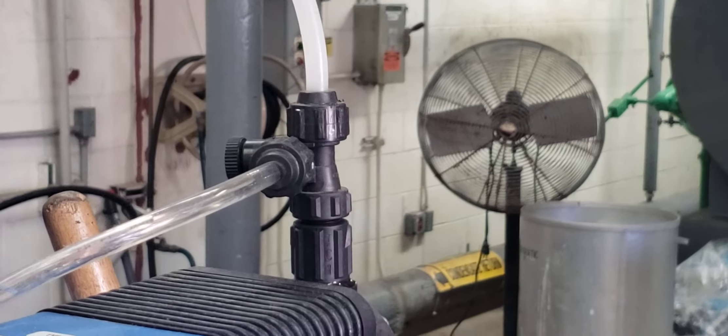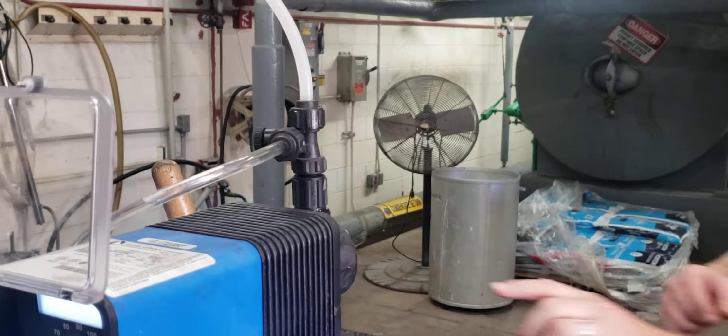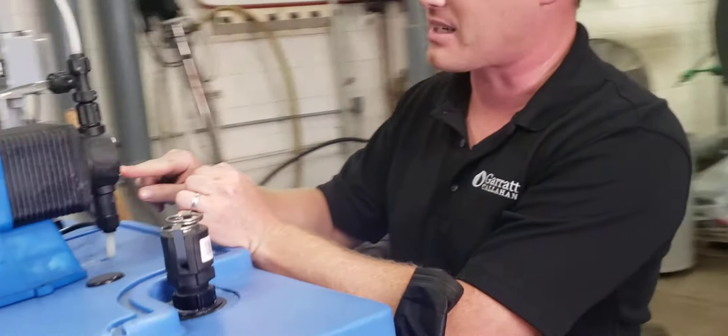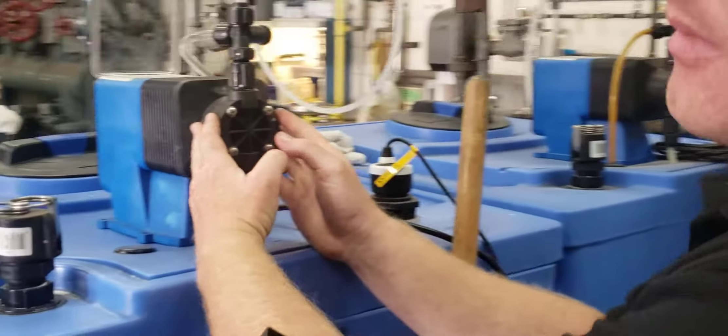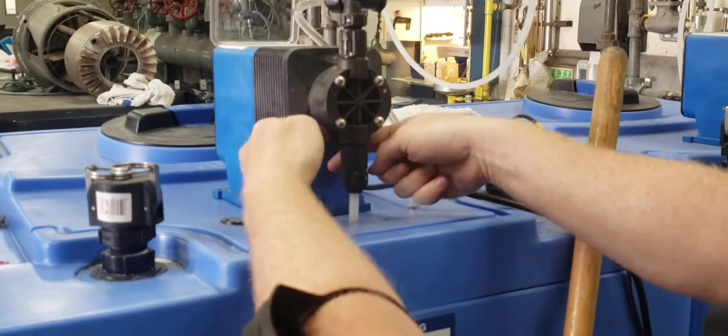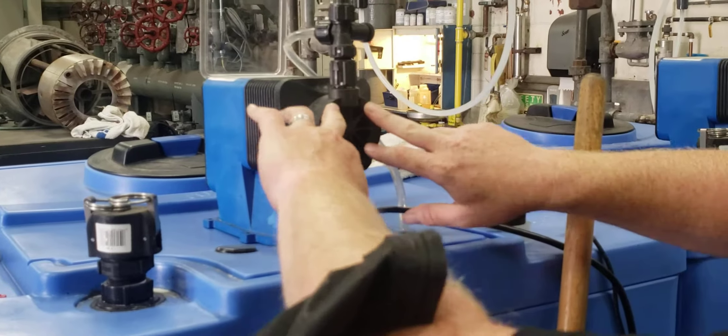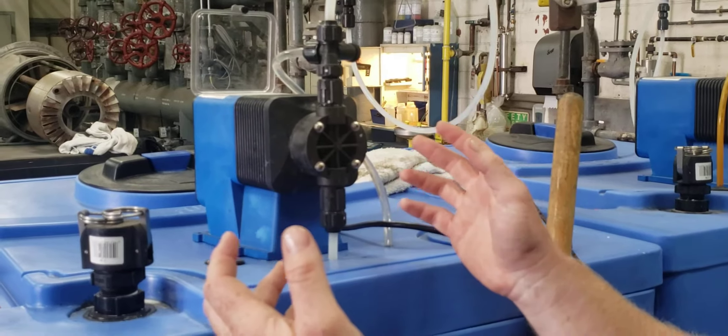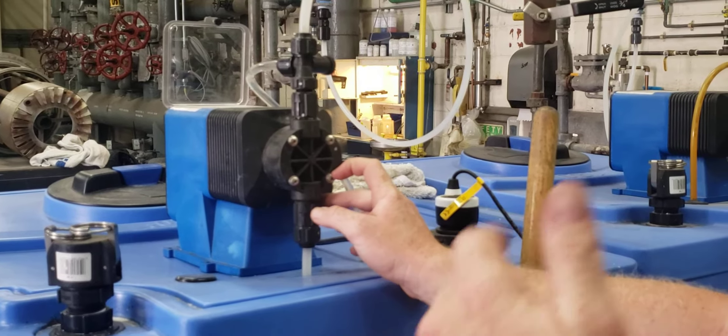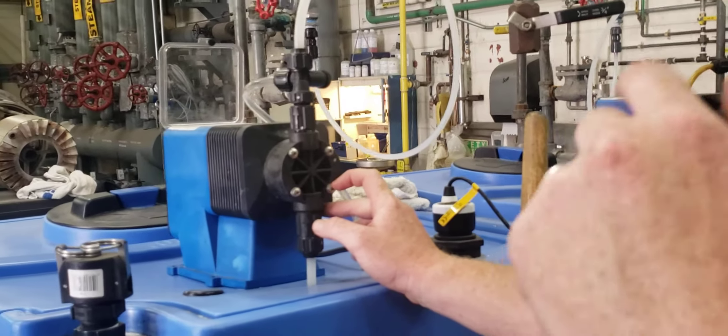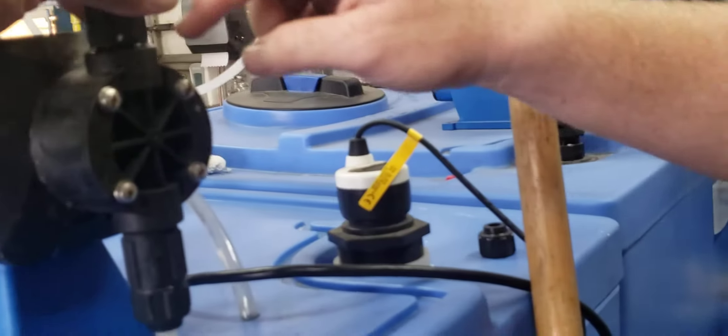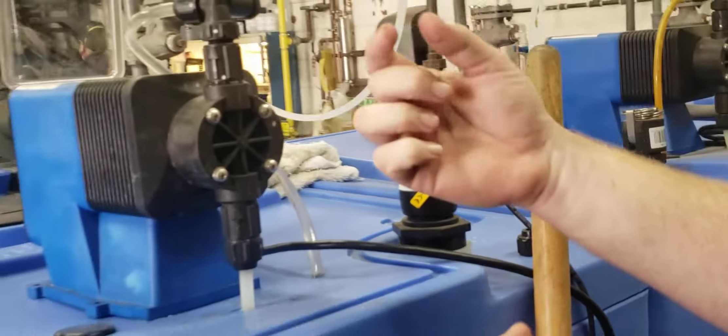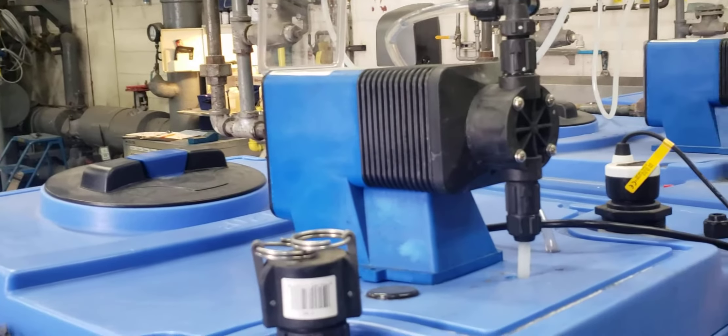Also I've noticed that sometimes there's four Phillips screws on the backside of this. Over time, if you start to see a drip from the bottom, these screws lose their tension over time. The guys actually asked me to have a quote for some rebuild kits. So I owe you guys that quote to have like three of those on hand. And you already can see this seal here needs to be tightened a little bit because it's losing a little bit of product.